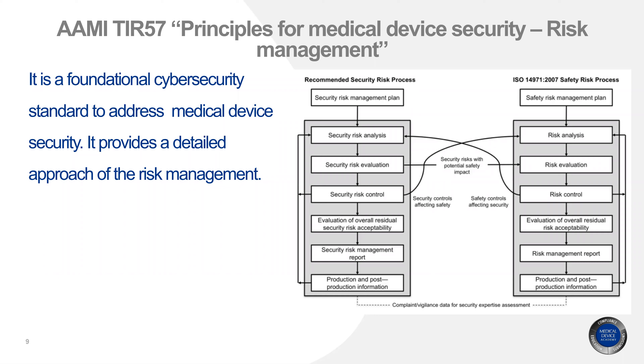One example is networked infusion pumps delivering fluids or medications — such as insulin, chemo drugs, or hormones — in a controlled manner. For safety, the pump receives regular software updates and the drug library gets updated with default dosage information. Imagine an attacker gaining access to the library — this leads to a change in dosage information and delivery of inaccurate doses to patients. If it's insulin being delivered, the patient may suffer from hypoglycemia, hyperglycemia, or diabetic ketoacidosis. This is how a security risk becomes a safety risk.